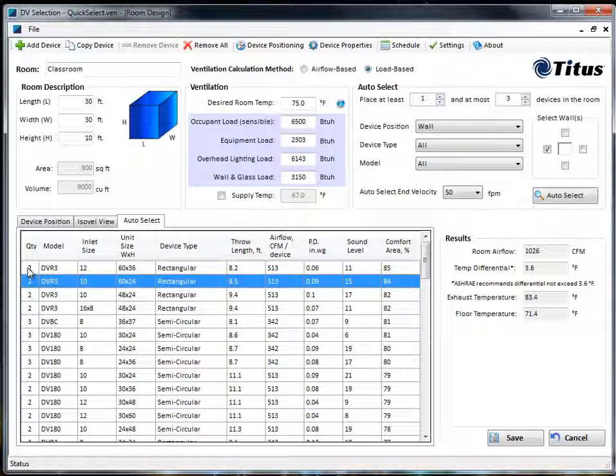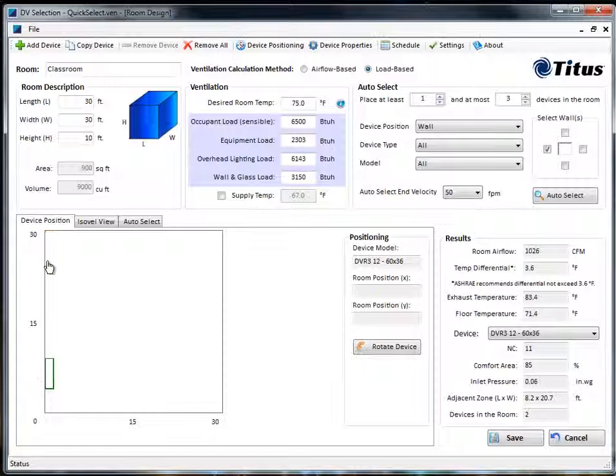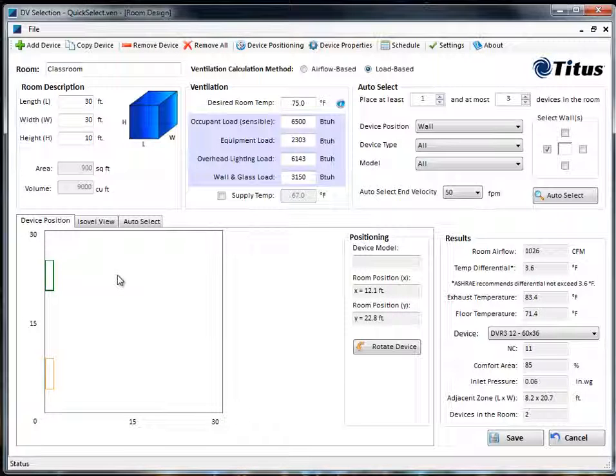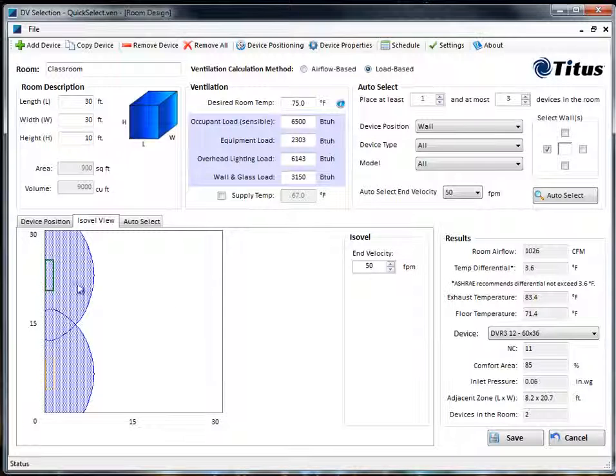Let's double-click on the first one and see how that looks. It opens up on the Device Positions tab. Let's move our diffusers centered on the wall here and now we can click on the Isovel view to see where the adjacent zone is. You can see here this is the adjacent zone with our end velocity set for 50 feet per minute — this is the area where you don't want to put occupants.